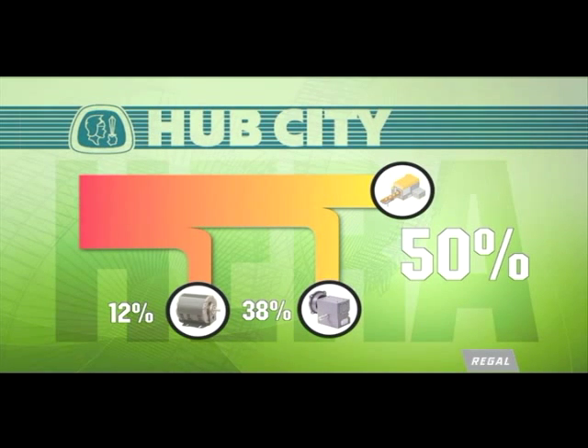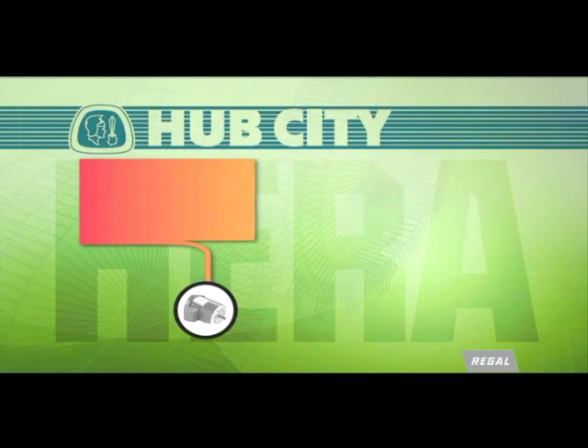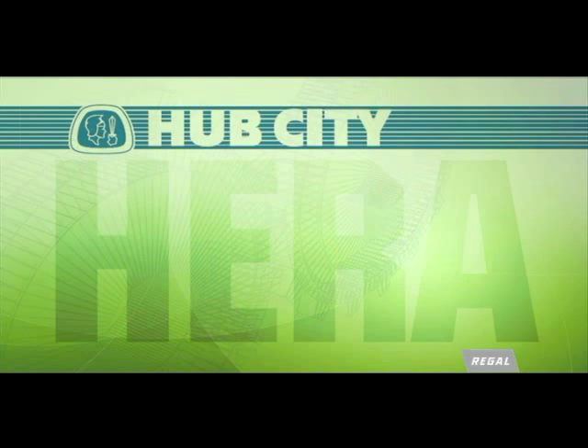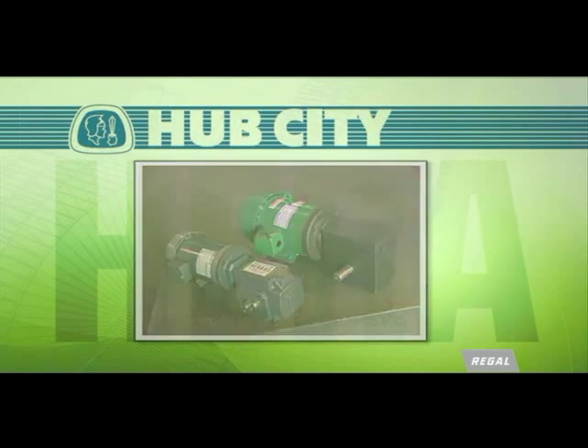Only 50% of the electricity you paid for is converted to usable power. With the HERA replacement strategy, combined with high-efficient electric motors, we now see that 10% of that power is lost due to the inefficiency of the electric motor, and a mere 9% is used to drive the HERA gearbox. This results in 81% of the electricity you paid for being put to productive use. The motor can be half the size, and HERA generates far less heat due to reduced friction.